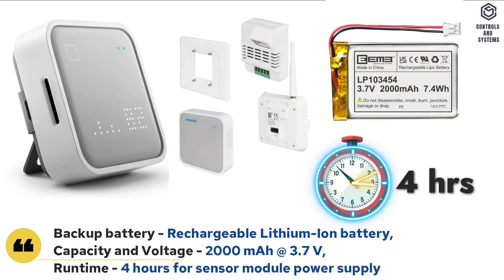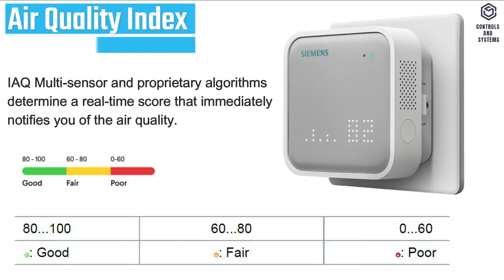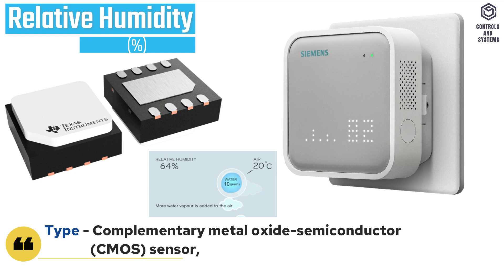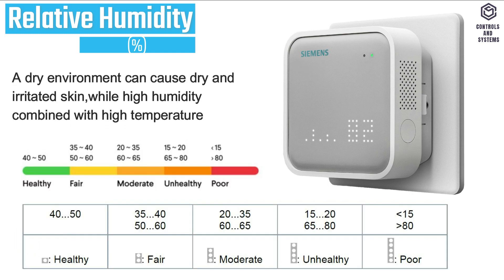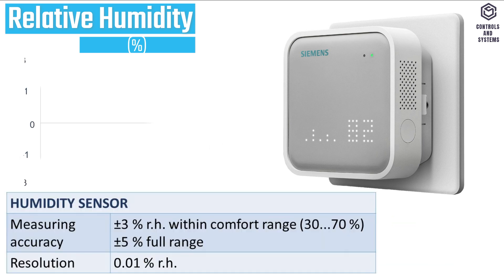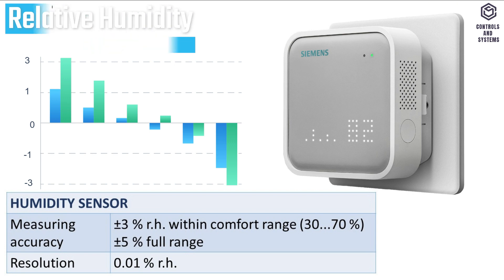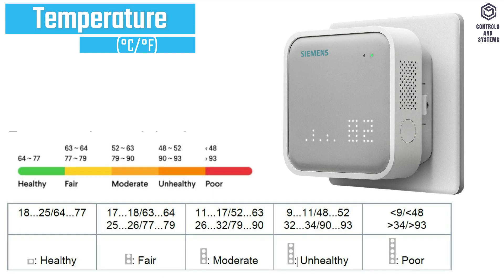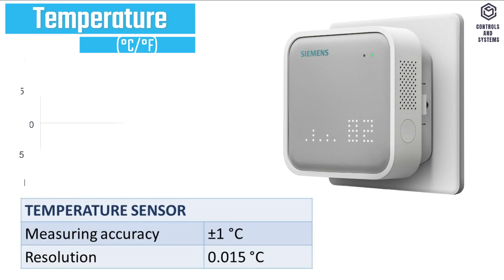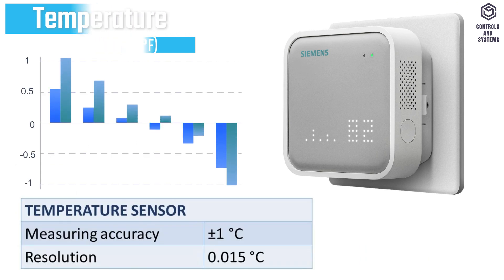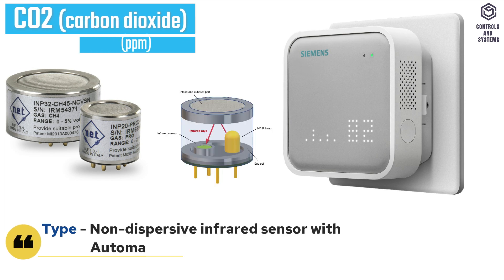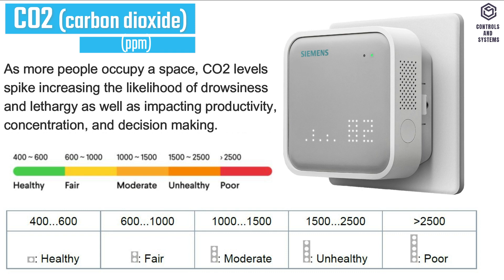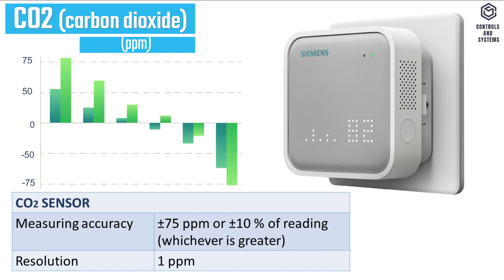Runtime is 4 hours for the sensor module power supply. Functional Data: Air quality depends on the LED colors shown in the table. Humidity sensor type is a complementary metal oxide semiconductor sensor, measuring range 0 to 100% RH. Temperature sensor type is also a complementary metal oxide semiconductor sensor, measuring range 0 to 90°C. CO2 sensor type is a non-dispersive infrared sensor with automatic baseline calibration, measuring range 400 to 5000 ppm. Measuring accuracy and resolution for each are shown in the respective tables.